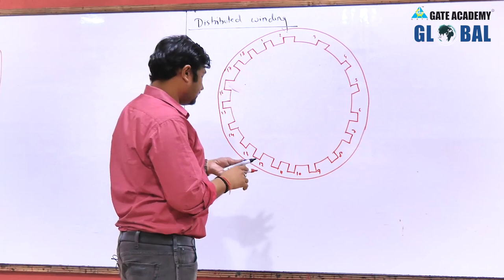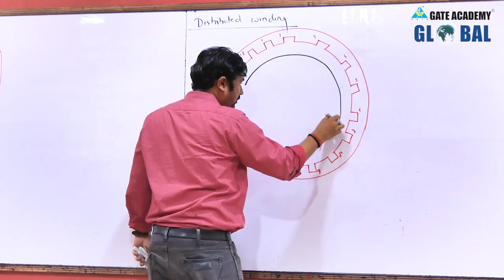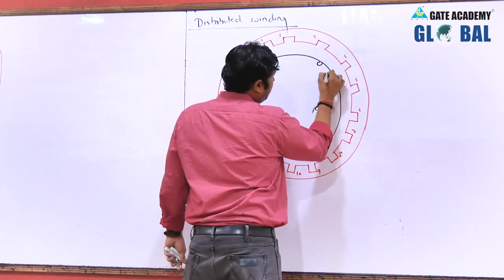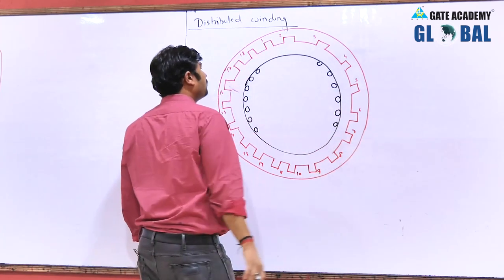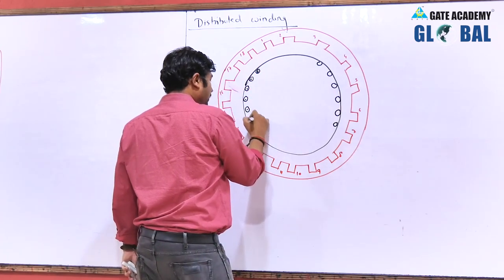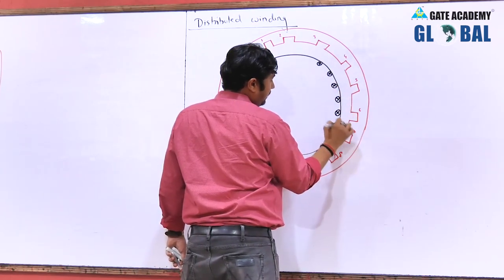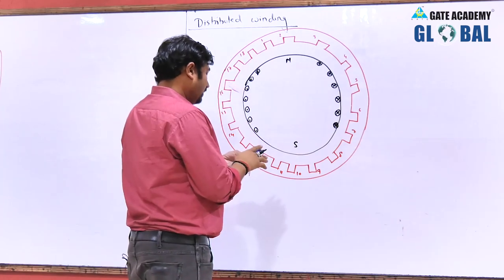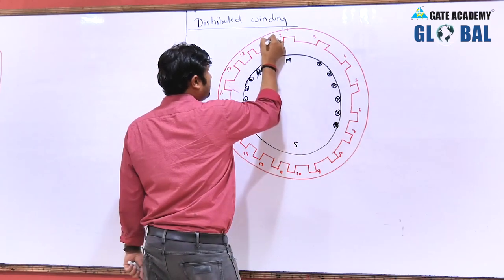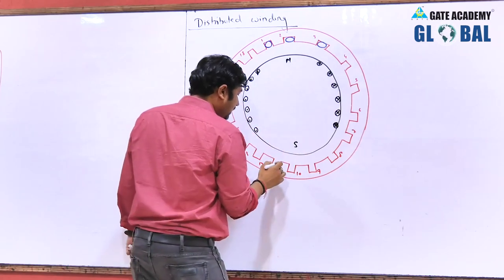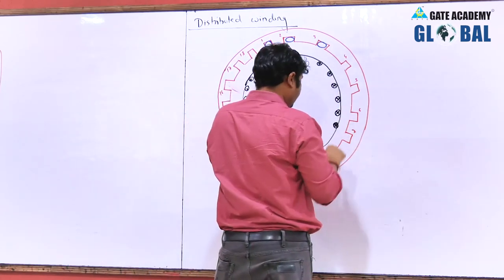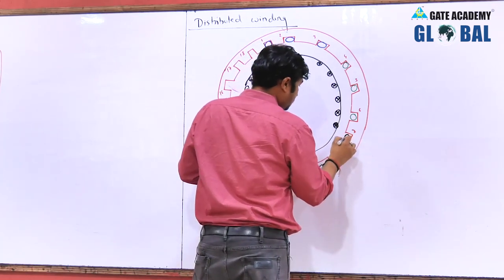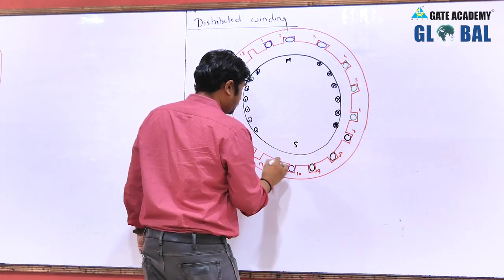We have 18 slots and the machine is 2-pole, meaning the rotor windings form 2 poles. The number of stator poles and rotor poles are always equal in a rotating machine. In distributed winding, the A phase winding is distributed into 3 slots instead of being in one slot. Similarly, B phase winding is distributed into 3 slots, and again A phase winding continues in this distributed manner.